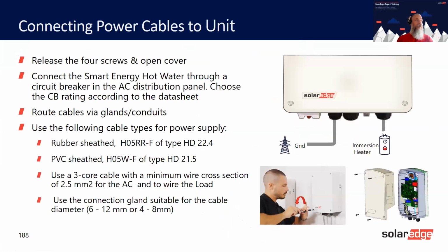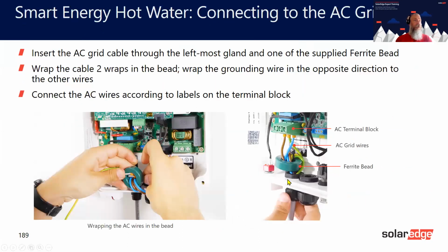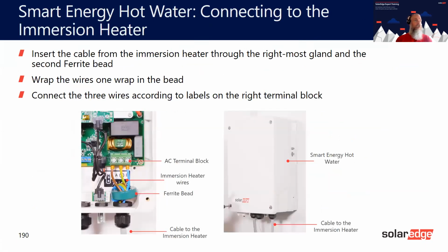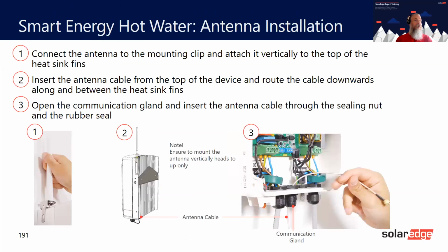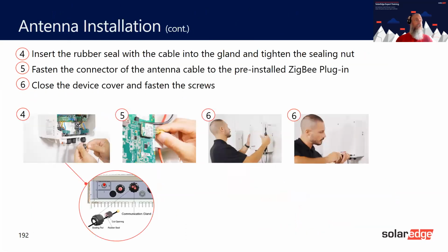What have we got on here? Just standard cable that you would use for immersion. Obviously, it's going to be close to the immersion. It can get hot. This is showing you wrapping around the cable. This is the communication. So this is the gland that you would poke through, and then you would terminate this onto the communication board for the antenna, just at the top here. And then don't forget to connect the antenna to the side of the inverter.